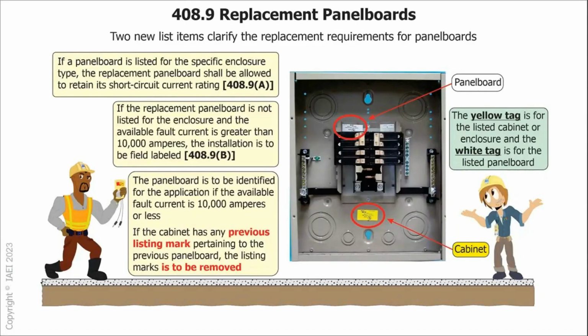So here we go. This is what we're talking about. You can see that the cabinet with the yellow sticker has one listing and the panel board has another. All right, so it's becoming more and more popular, especially with these indoor panels, to just replace what we call the guts, which the code calls the panel board. And that panel board is going to have the same short circuit current rating, right? So the panel board is identified for the application if the available fault current is less than 10,000. If the cabinet has any previous listed markings pertaining to the previous panel board, the listing mark is to be removed.